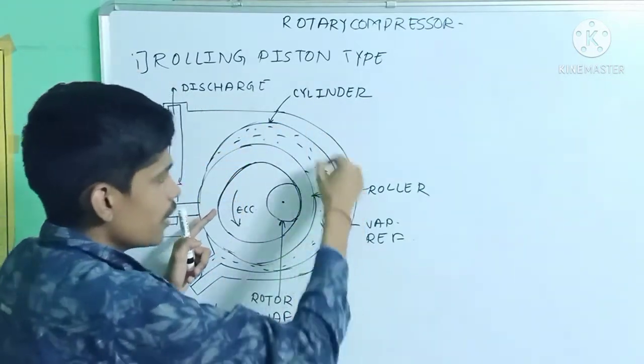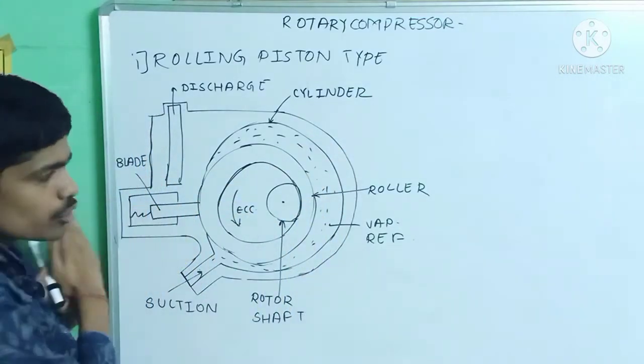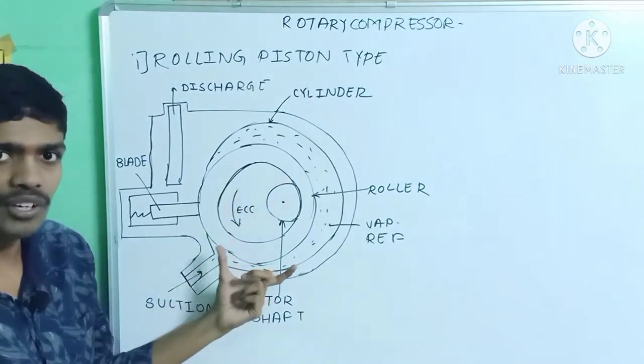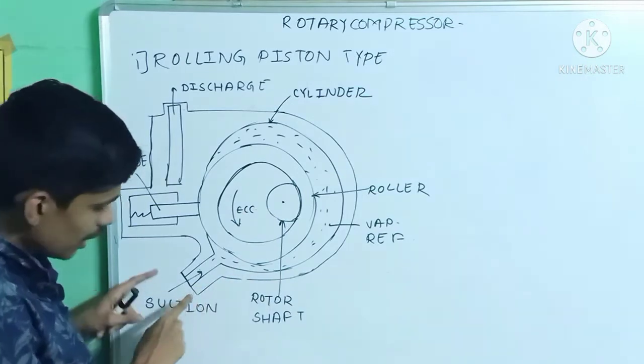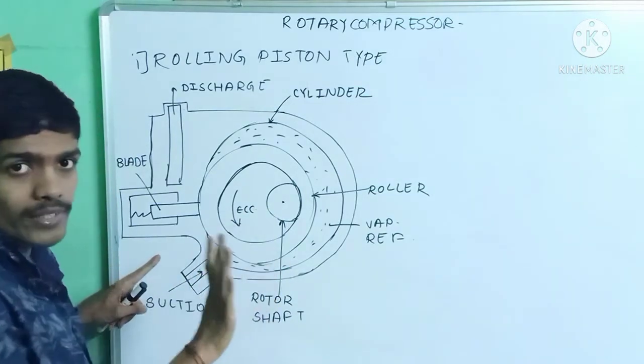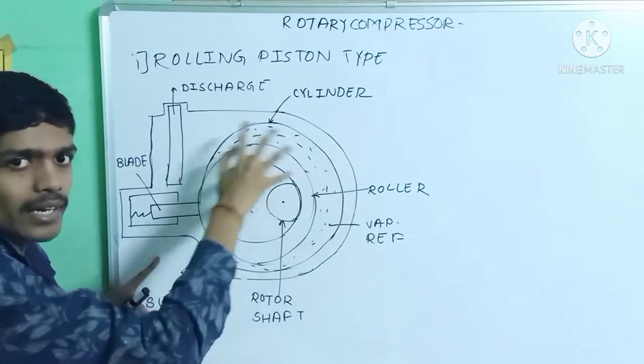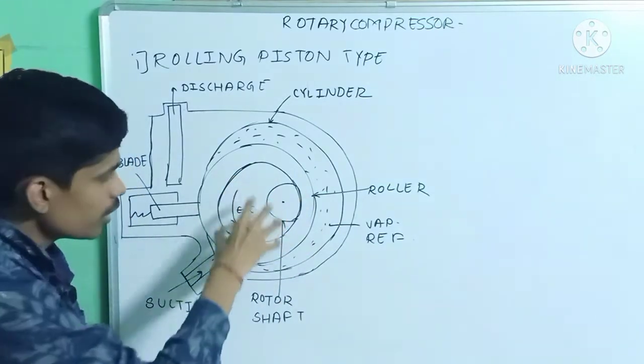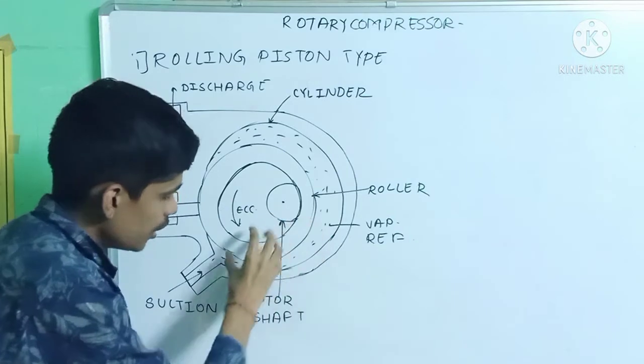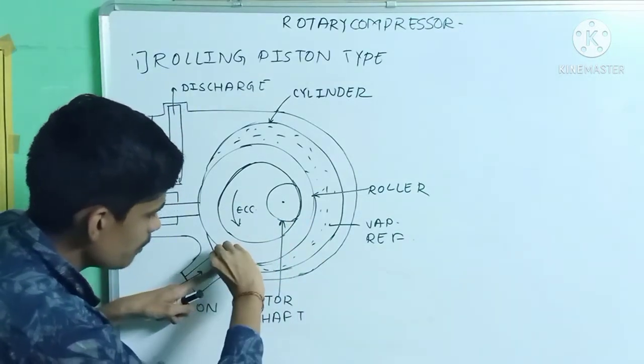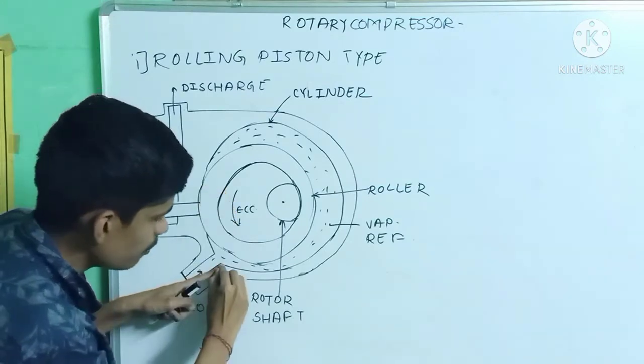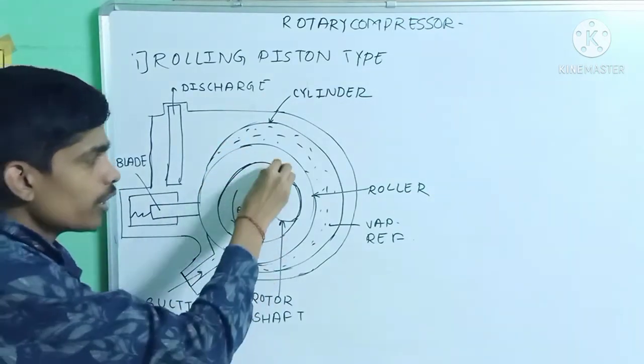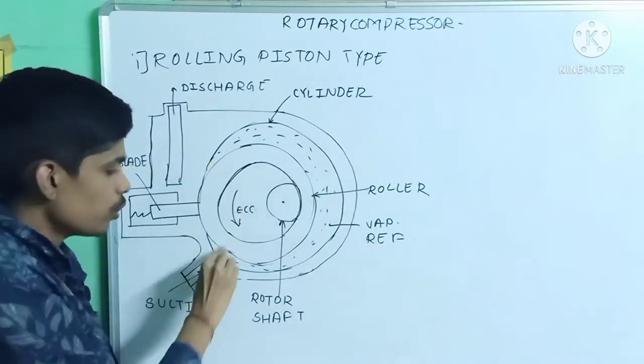The blade moves in and out as the roller rotates. There are generally four cases, but one figure is explained here. When the suction stroke is completed, vapor refrigerant is inside the cylinder. As the roller starts rotating, the blade moves and whatever vapor refrigerant is ahead of the roller gets compressed because there is a small annular space between the cylinder and the roller.